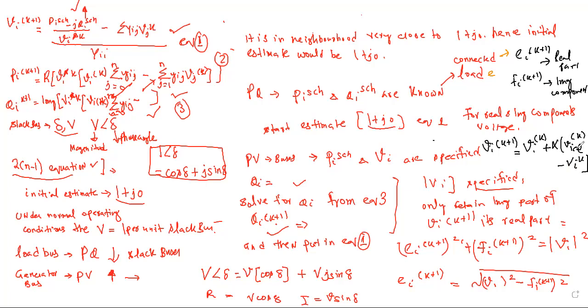Its value will depend upon the system. Okay, so in typical calculations, it is found to be around 1.3 to 1.7, usually for the Gauss Seidel method of this calculation. This is the value of rate of convergence, so it will converge. Otherwise, you have to do more number of iterations. If you don't take the value of alpha, you have to do more number of iterations.